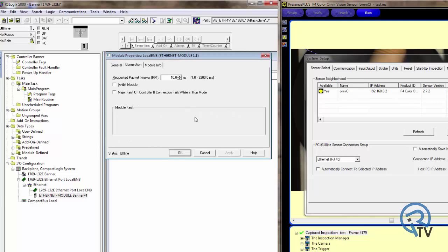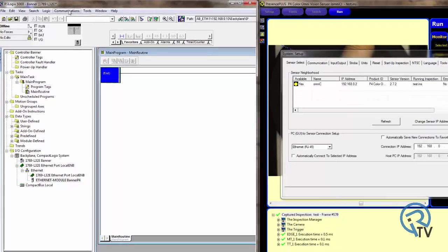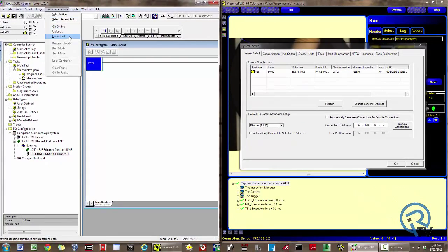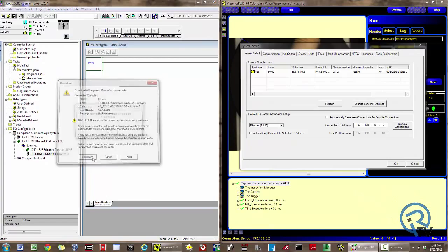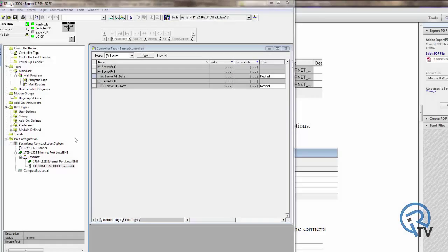Press OK, and then under the RPI, choose an RPI of 100 milliseconds. Simply go ahead and download your program. Now that I've downloaded and I'm online, take a look back at your generic module and make sure there are no errors, no flags, and the status says running.